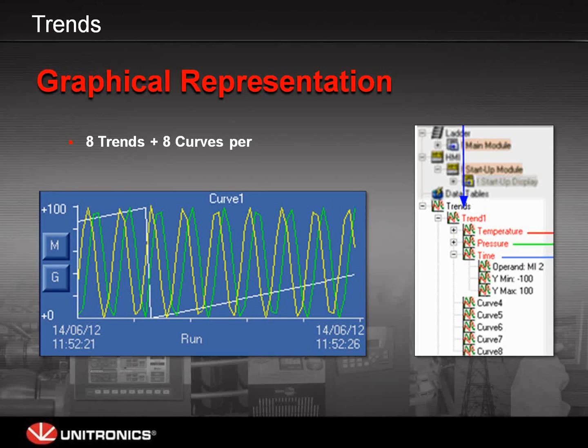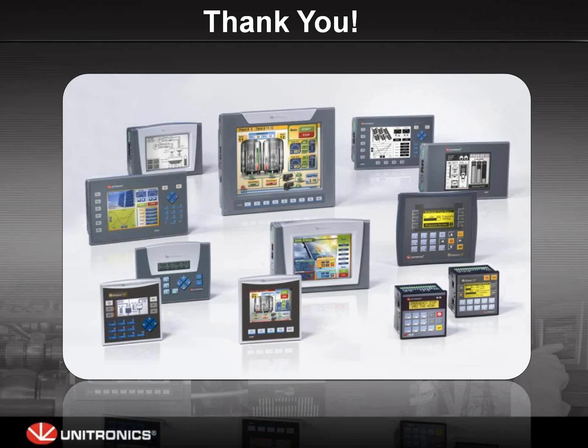We'll take a look at graphical representation of data. If you have the analog input coming in and it's been scaled, you want to show that on the HMI of the controller. We have the option for trends as well as meters and bar graphs. The trends allow you to have on a 570, 560, or 1040, a total of 8 trends with 8 curves per trend. You can have 8 different graphic variables with 8 curves on each line, giving you the ability to represent a total of 64 memory integer values linked to analog input values.